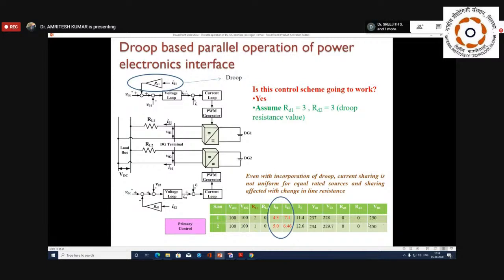It should be 228, not 250. Sorry for that. This VDC should be 228, and the second condition is 229.7. So now this common DC link voltage is not 250 volt, it's 228 and 229.